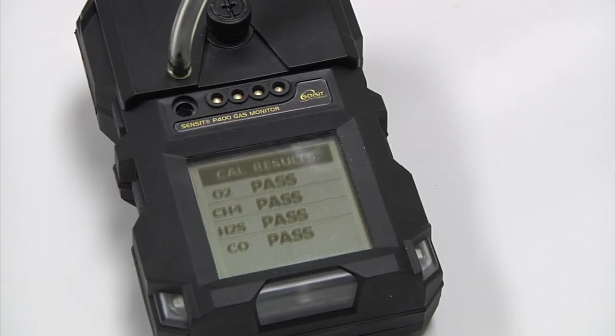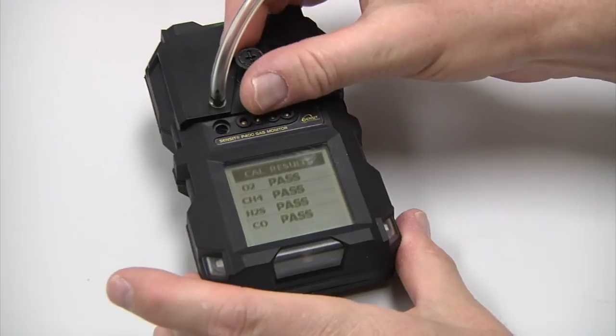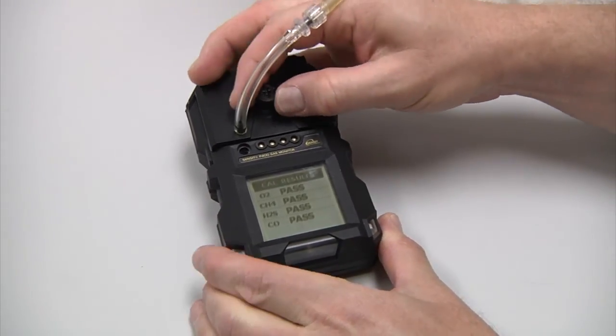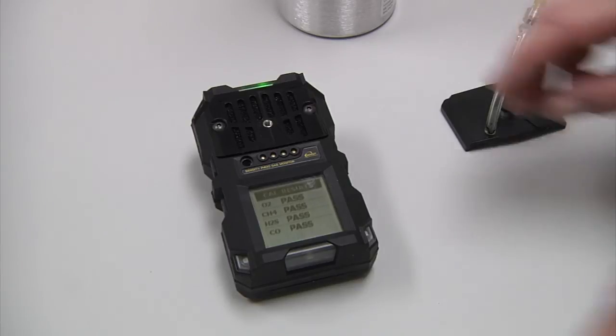Go ahead and turn the regulator off and take the cal cup off the instrument. Now if something failed to calibrate, it would be indicated here as a failed. If it does fail, you're going to want to let the instrument clear, re-zero it, and then try the calibration for the second time. You can press the O button to exit this screen.